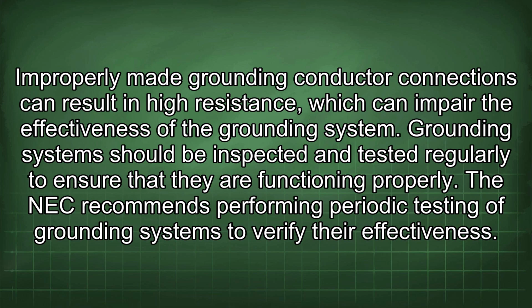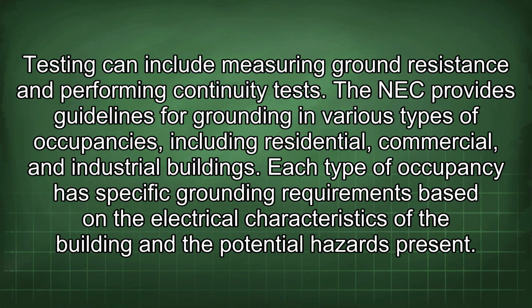Grounding systems should be inspected and tested regularly to ensure that they are functioning properly. The NEC recommends performing periodic testing of grounding systems to verify their effectiveness. Testing can include measuring ground resistance and performing continuity tests.